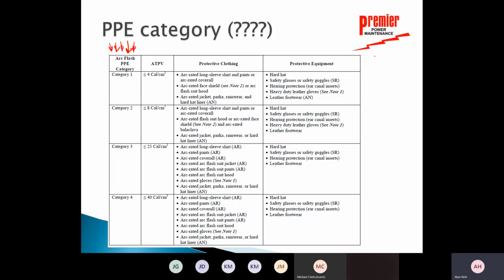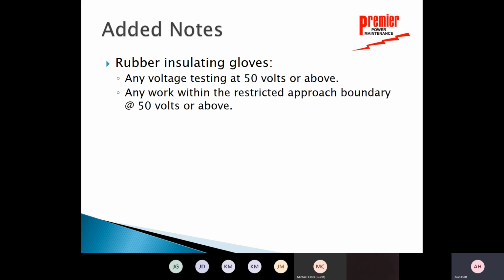Basically, again, if it's greater than or equal to 1.2 calories, but less than or equal to 8 calories, your clothing's acceptable. If it's greater than 8 calories, but less than or equal to 40 calories, then we're using the arc suit, the beehive suit. Everything else stays the same with hard hat, safety glasses, hearing protection, leather gloves, leather footwear. We've got our balaclava on, those sorts of things. So that's their chart. Then the only other thing I want to add to this is rubber insulating gloves.